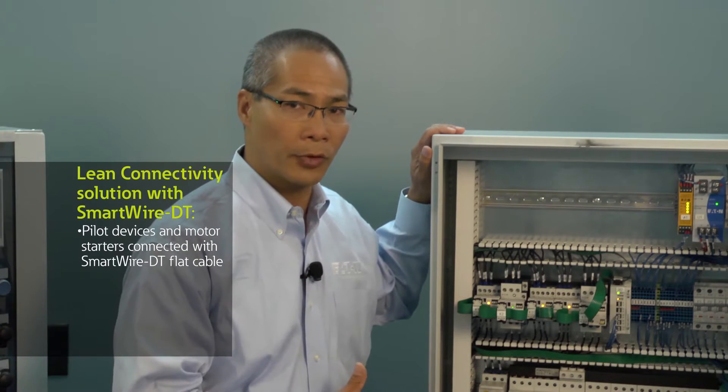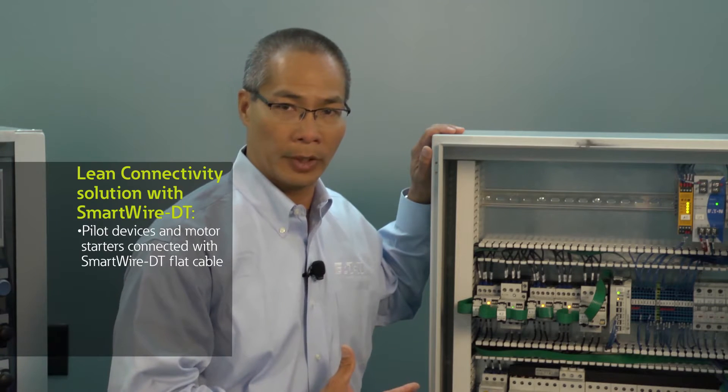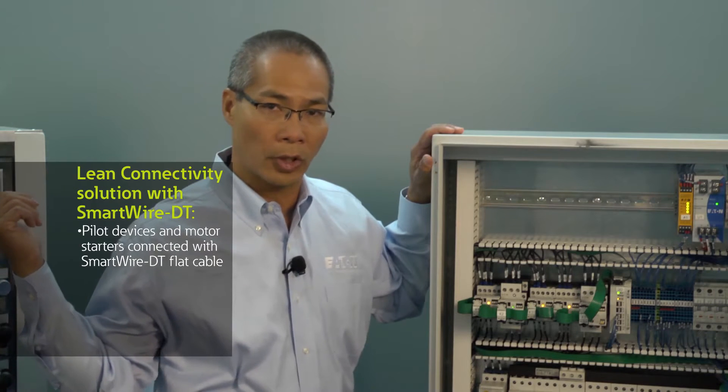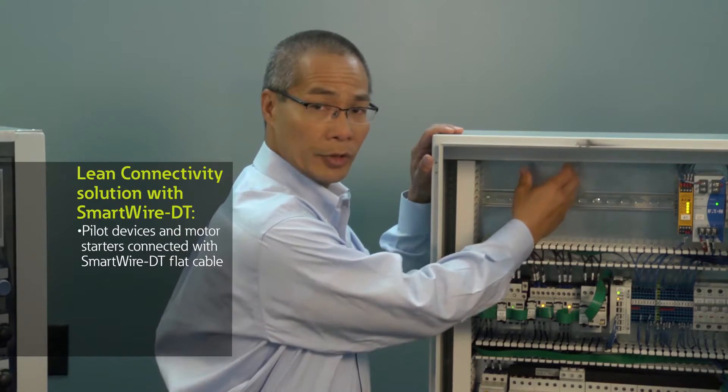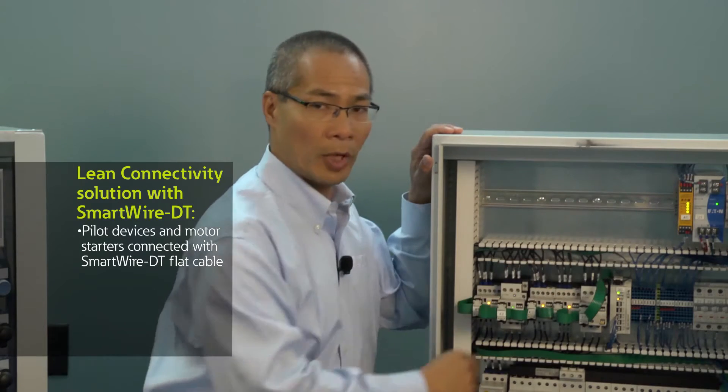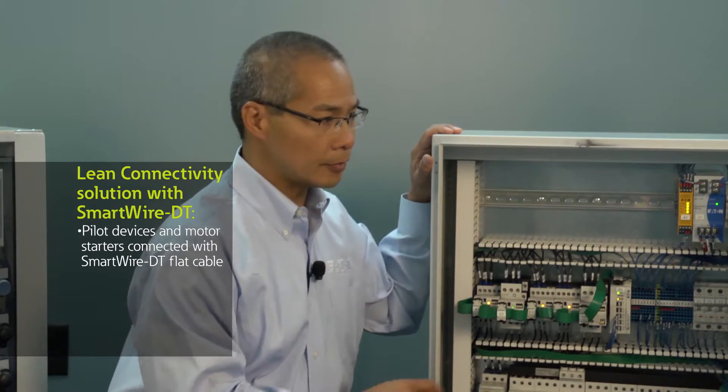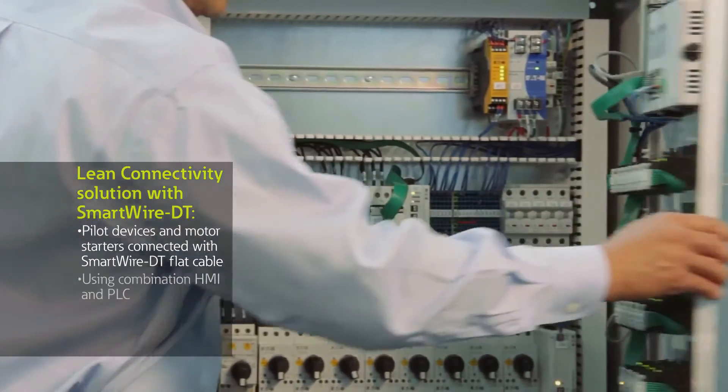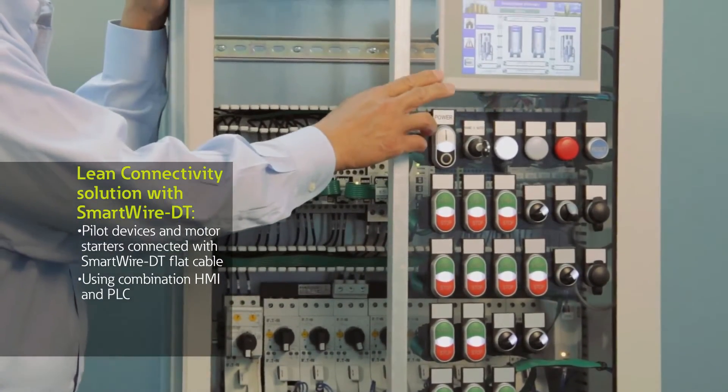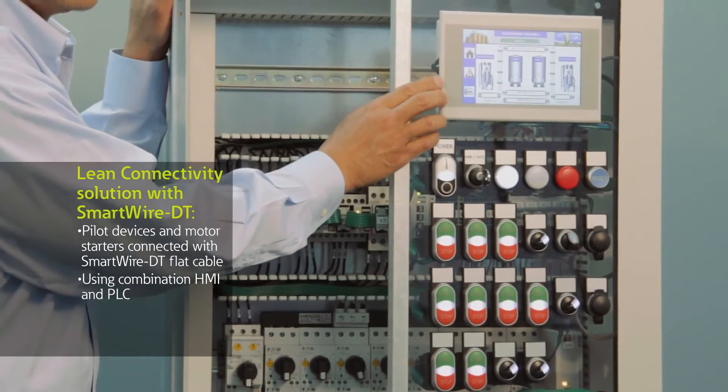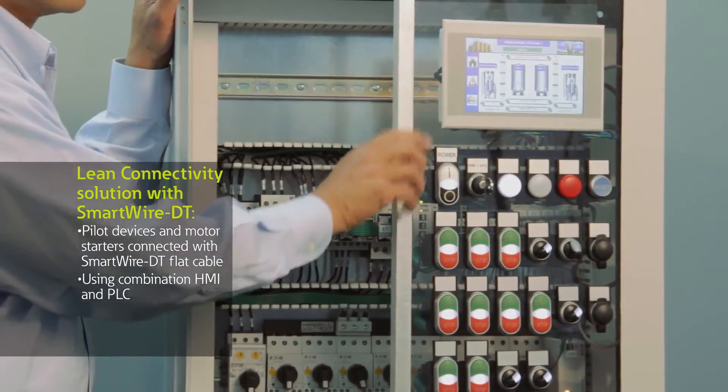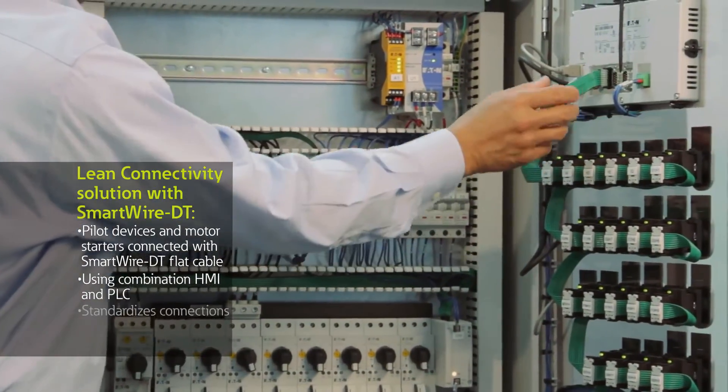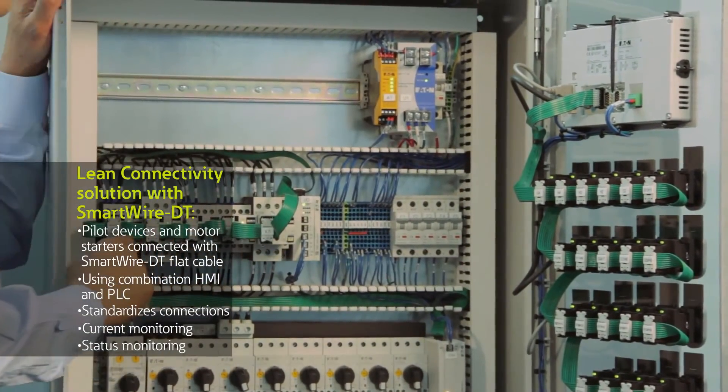SmartWire DT works with any third-party PLC through the use of what we call a gateway. For example, I could still have the same PLC CPU located here with an additional gateway solution wired to my flat green cable. In this instance, what I've done is actually included the PLC functionality inside my HMI PLC, so all the logic is being run from this particular unit. It's a combination PLC and HMI in one. In addition, the gateway to the SmartWire DT system is actually built in, so the flat cable can plug directly into the back of the HMI PLC.